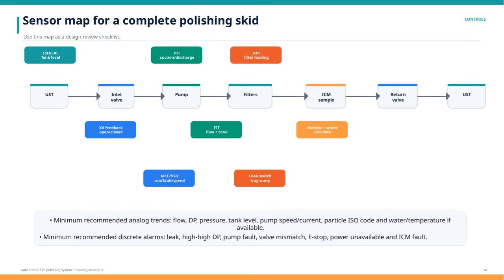The motor control center and variable speed drive provide real-time run status, fault alerts, and speed information for the pump. This feedback is essential for maintaining performance and addressing issues proactively. We recommend continuously trending key analog signals such as flow, differential pressure, overall pressure, tank levels, and pump speed or current to identify anomalies early.